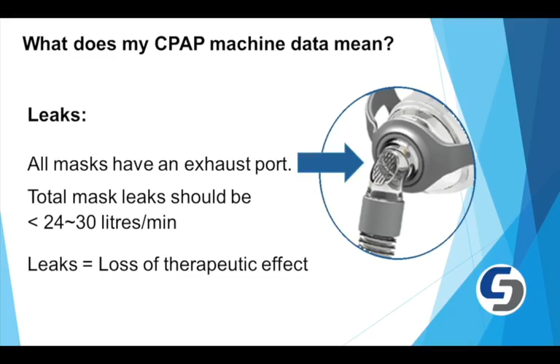Some common feedback we get from new patients is that they think the pressure is too strong or the machine is blowing a gale. Now, CPAP machines with fixed pressure are set to a treatment pressure. This is prescribed by the doctor, and it is the pressure that your body needs to keep your airway open. This pressure is different for every patient. Usually practice before starting CPAP therapy will help immensely. If patients can't get used to the treatment pressure that's required, then a ramp or a lower starting pressure can be enabled. This will help patients receive a lower treatment pressure to begin with and will slowly increase over the ramp time. The ramp time is typically how long it takes the patient to fall asleep.